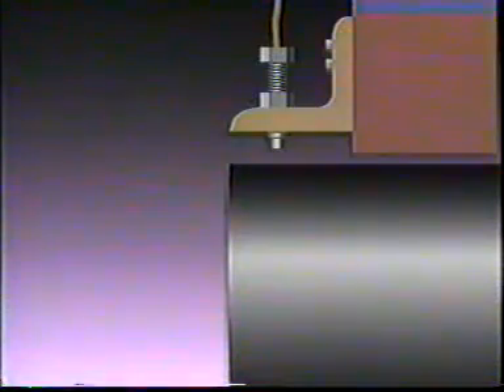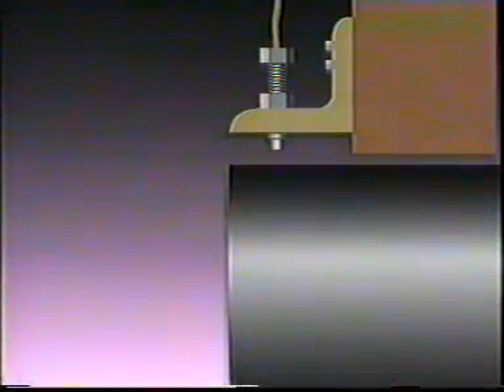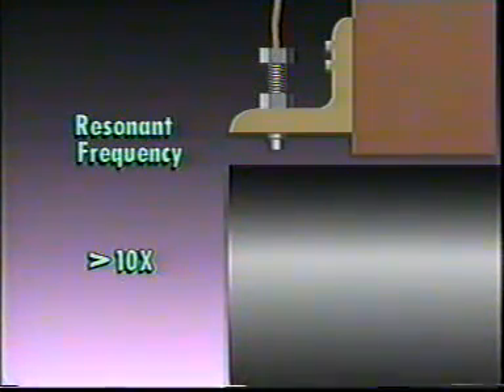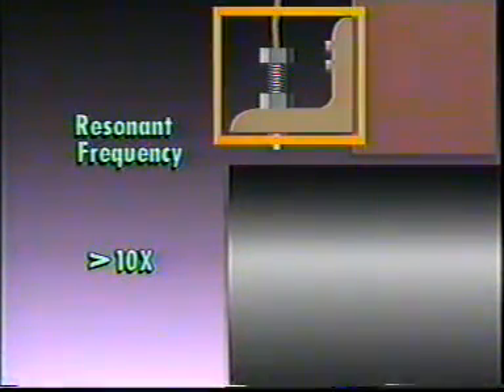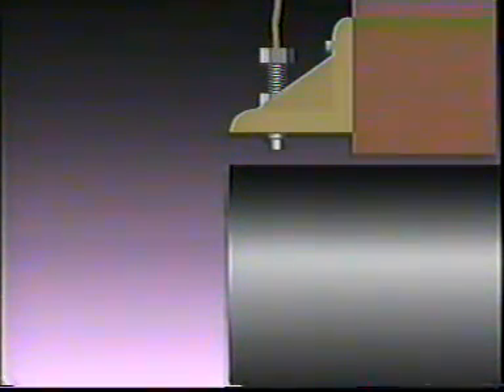Bracket selection and sizing is important to prevent false readings during machine operation due to casing vibrations transmitted to the bracket. Brackets should have a resonant frequency at least 10 times greater than the rotational speed of the machine to prevent the probe from vibrating. Also, the shape of the bracket is significant. Longer angled brackets should not be used without a gusset. The gusset will keep the perpendicular leg from vibrating at a frequency different from the machine casing.